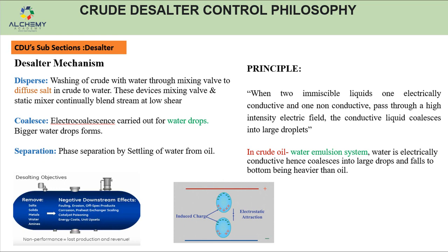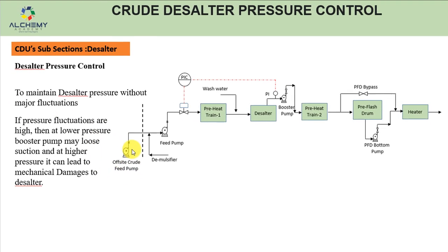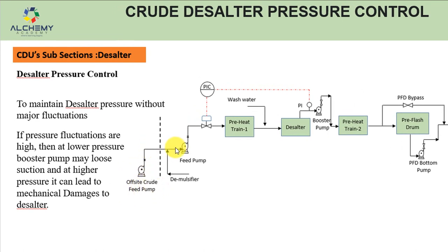The basic desalter mechanism uses three stages: disperse, coalescence, and separation. For the disperse stage, crude comes from the refinery tank farm via an offsite crude feed pump, then to the CDU unit feed pump. From the feed pump discharge it goes to the preheat train. One control valve on the feed pump discharge basically controls the desalter pressure. The preheat train heats the crude coming from the tank farm to the desalting temperature — this is important to reduce viscosity and increase fluidity so that water mixes properly.